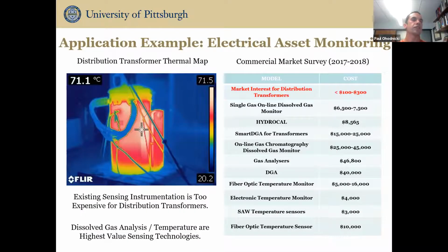A key application for this in energy infrastructure monitoring is transformer monitoring. In large transformers, one of the key ways you measure the state of health is based on the insulation oil. You measure local temperature and chemistry, and if you start to see hydrogen or hydrocarbons, that's a signature the insulation oil is degrading. For large transformers, companies pay upwards of tens of thousands of dollars to monitor this in real time.